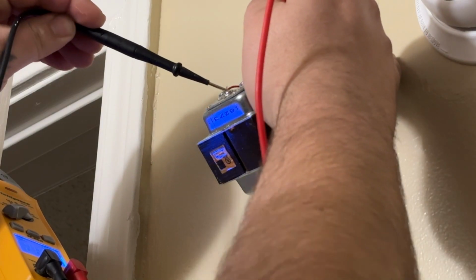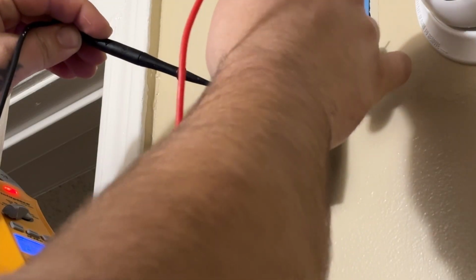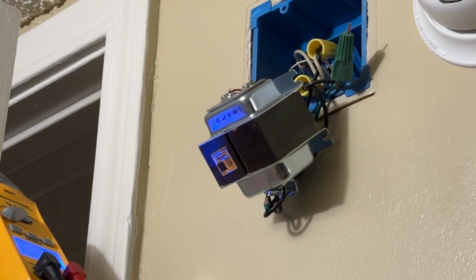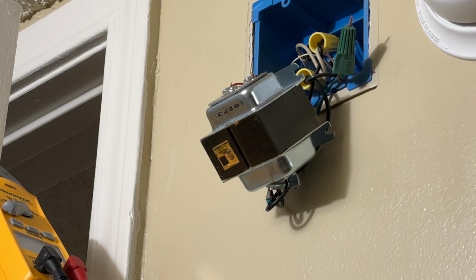Testing between these two, we have 28.42. Right at 30 volts. Now we need to test the low voltage side of this transformer while it's under load, which means activating our audio-visual siren with the pull cord.